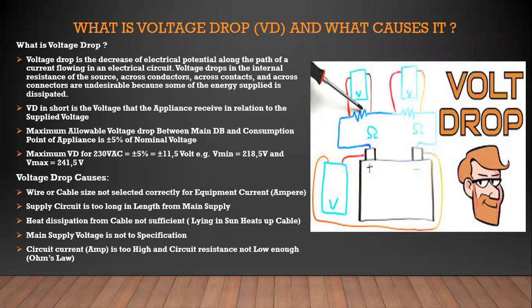Typically, the cable size is not correct, or the circuit is too long. You might find the client will give you a call out, and the problem you experience is the water doesn't get hot as much as it should. Voltage drop could be one of the causes. If the circuit is too far from the main board to the geyser, you get a huge voltage drop if the wires are not selected correctly, and your element doesn't get the appropriate voltage it's designed for, to have an output of, for example, 3000 watt. It might put out 2000 watt, and hence the water won't heat up properly like it should. So voltage drop causes are specified, how to determine it, and what to look out for.